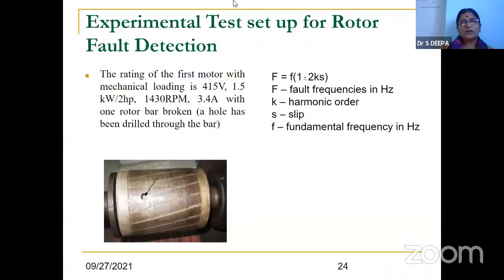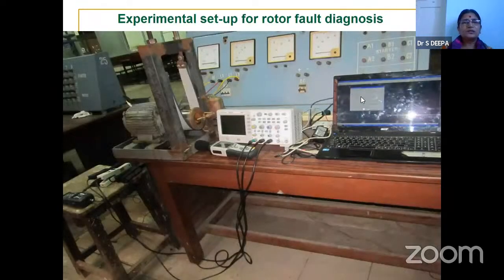So next is the rotor fault. So in the rotor fault also, experimental test setup for rotor fault detection. Here we have the rating of the first motor with mechanical loading, 415 volt, 1.5 kilowatt or 2 HP. And so here the fault frequencies, when the fault occurs, what frequency will be there, the calculation formula. So this is the setup for rotor fault.